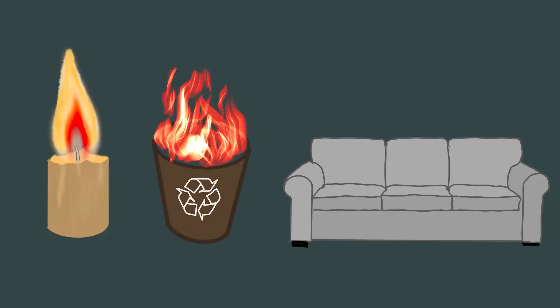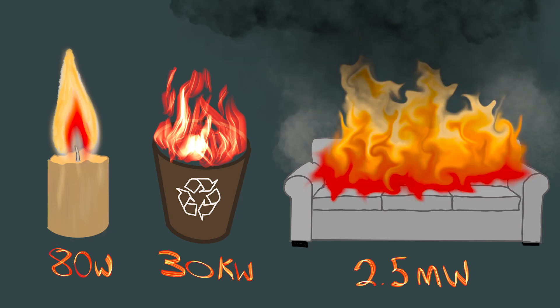So if you take these fuel sources for example, they will all burn with a similar flame temperature. But the candle will release around 80 watts of energy, the rubbish bin will release around 30 kilowatts of energy, the sofa will release around 2.5 megawatts of energy, and a room that has gone through flashover will release in excess of 5 megawatts of energy.